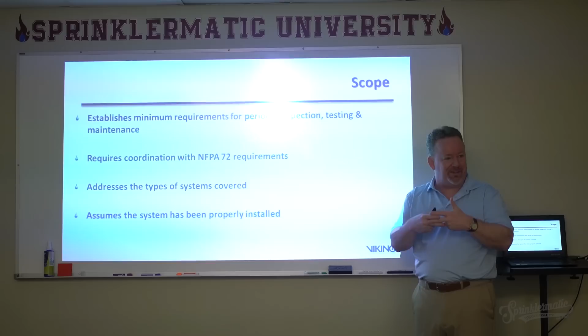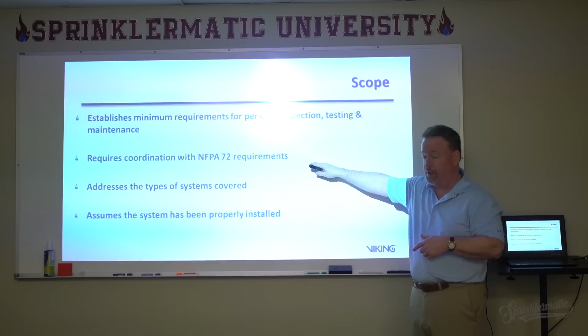NFPA 72 has its own inspection, testing, and maintenance requirements, and they don't always jive with NFPA 25. So we have to make sure that we're making that work. NFPA 25 in its scoping section actually says you're going to play along with 72 on this as well. It addresses the types of systems that are covered: water-based fire protection systems.